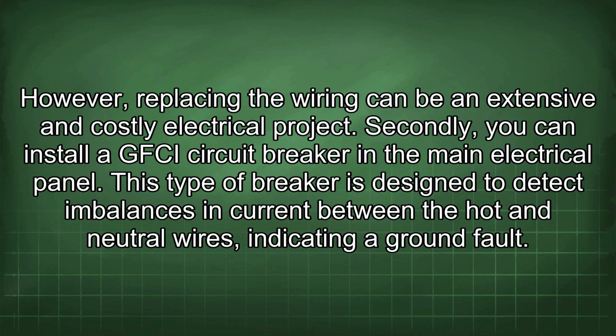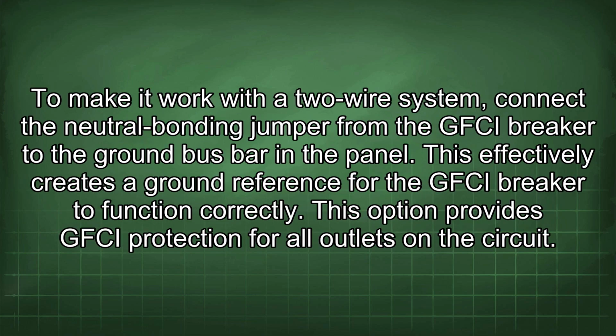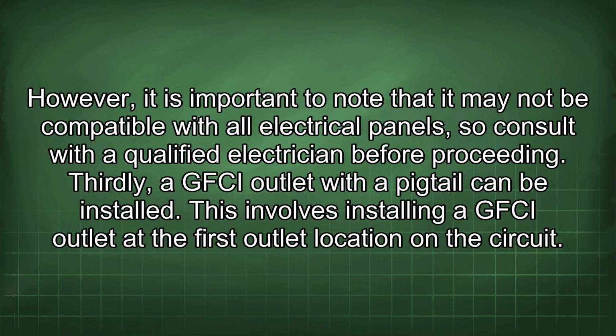Secondly, you can install a GFCI circuit breaker in the main electrical panel. This type of breaker is designed to detect imbalances in current between the hot and neutral wires, indicating a ground fault. To make it work with a two-wire system, connect the neutral bonding jumper from the GFCI breaker to the ground bus bar in the panel. This effectively creates a ground reference for the GFCI breaker to function correctly. This option provides GFCI protection for all outlets in the circuit. However, it is important to note that it may not be compatible with all electrical panels, so consult with a qualified electrician before proceeding.